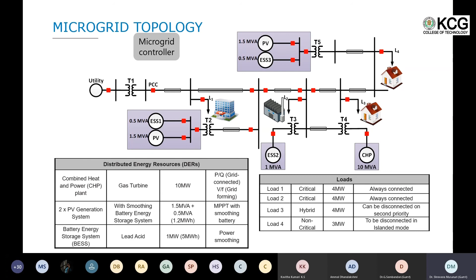Now, how does that happen? The microgrid controller always keeps track, taking information from each of the IEDs, second by second: what power is flowing through each device, what the total load is, and so on. Then it runs its EMS application algorithms and gives the necessary set points.